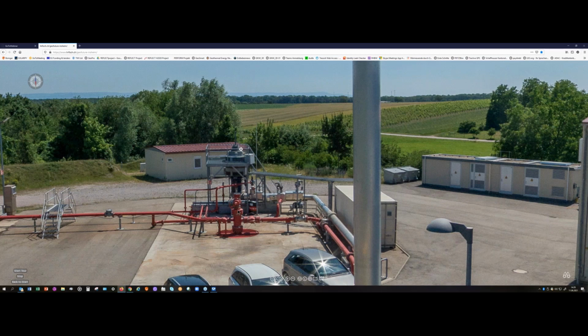Okay, thanks. What kind of maintenance work is needed for a line shaft pump? By itself, the line shaft pump can be operated almost maintenance-free. As I mentioned, the line shaft itself has to be constantly greased. But once the pump is installed and carefully operated, we expect, for our next overhauled pump, an operational period of about 7, maybe even 10 years.